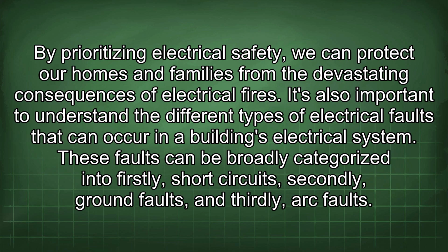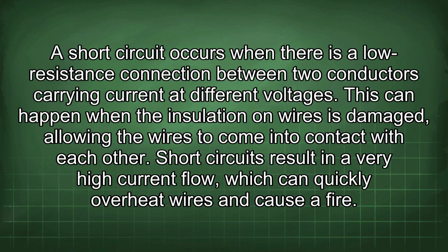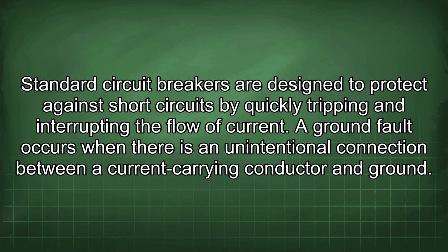It's also important to understand the different types of electrical faults that can occur in a building's electrical system. These faults can be broadly categorized into firstly, short circuits, secondly, ground faults, and thirdly, arc faults. A short circuit occurs when there is a low resistance connection between two conductors carrying current at different voltages. This can happen when the insulation on wires is damaged, allowing the wires to come into contact with each other. Short circuits result in a very high current flow, which can quickly overheat wires and cause a fire. Standard circuit breakers are designed to protect against short circuits by quickly tripping and interrupting the flow of current.